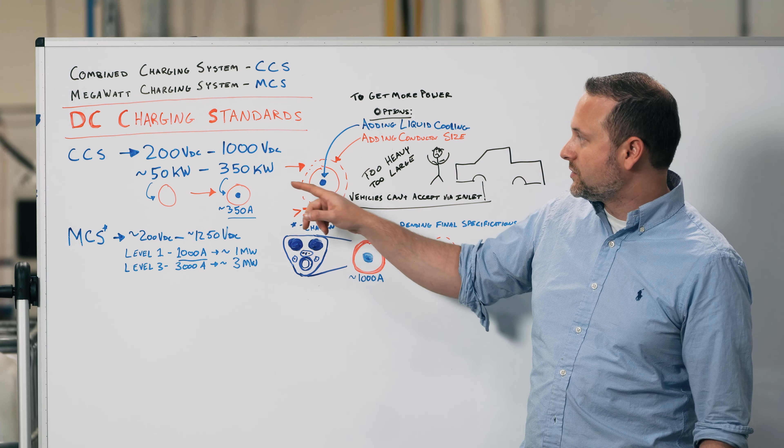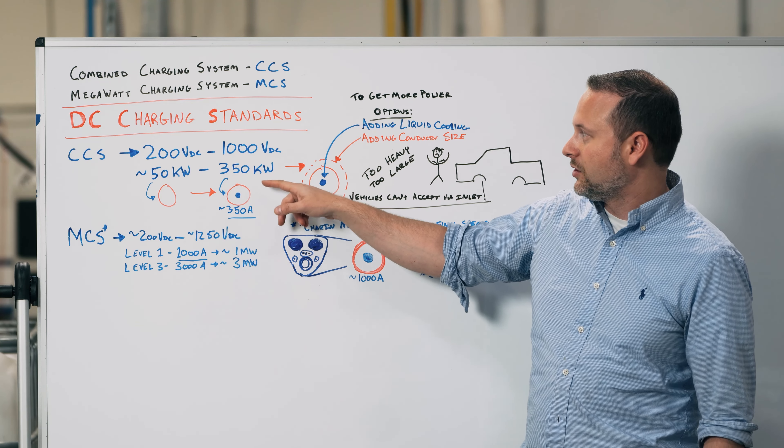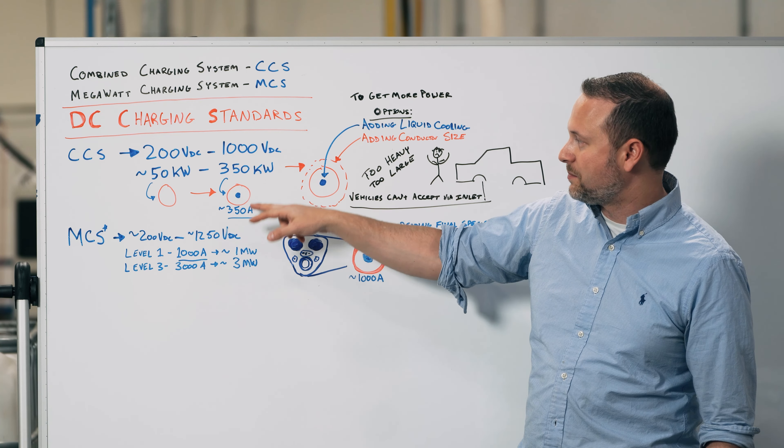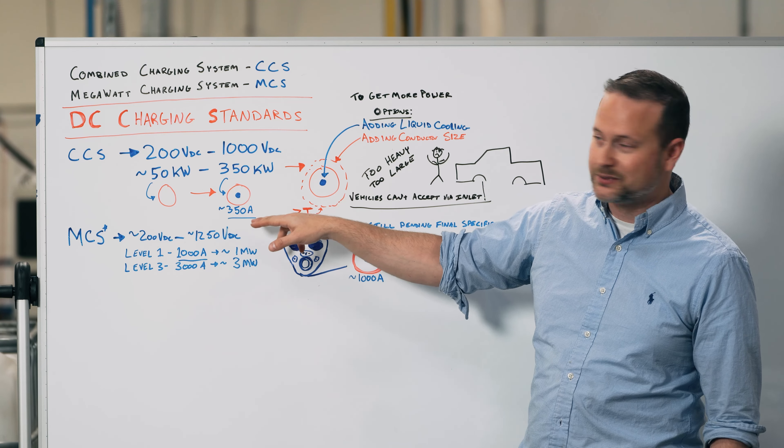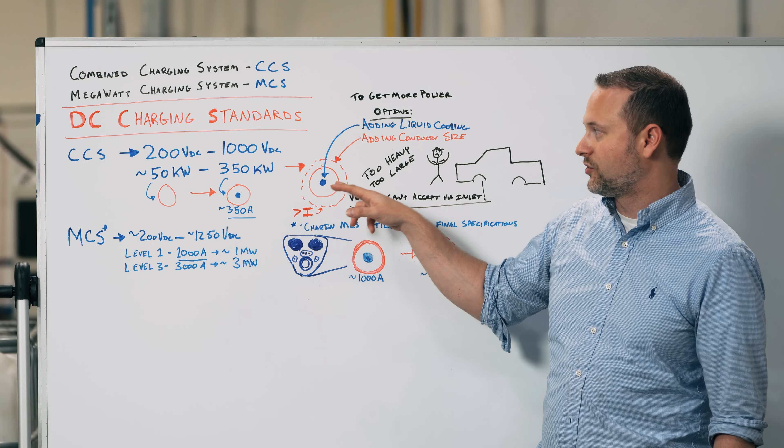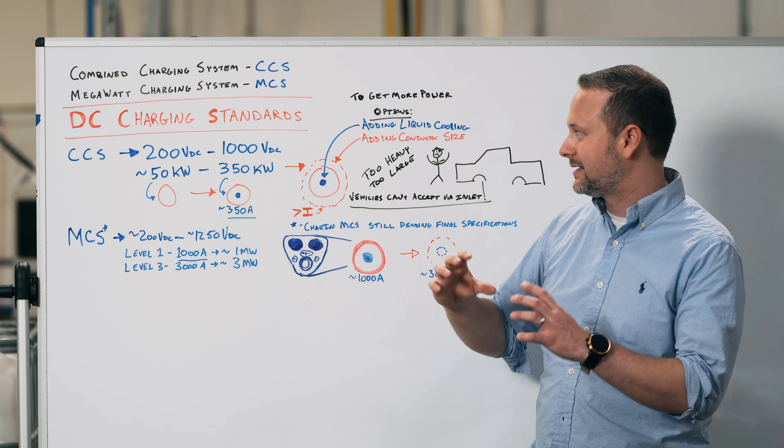Now, in order to achieve 1 megawatt in the CCS standard, the only option that you have is to increase the current to beyond 1,000 amps, or roughly about 1,000 amps. And in order to do that, you're going to have to extend the size of the cable.